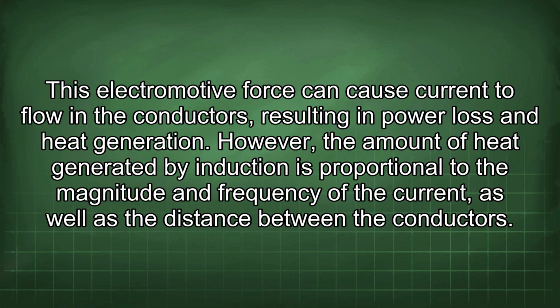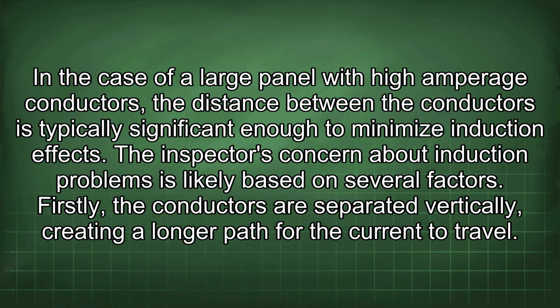However, the amount of heat generated by induction is proportional to the magnitude and frequency of the current, as well as the distance between the conductors. In the case of a large panel with high amperage conductors, the distance between the conductors is typically significant enough to minimize induction effect. The inspector's concern about induction problems is likely based on several factors.